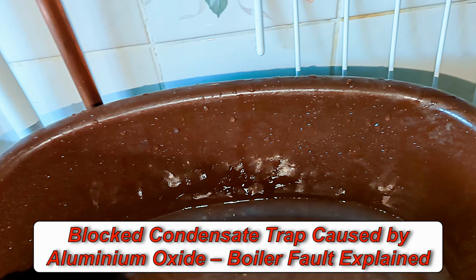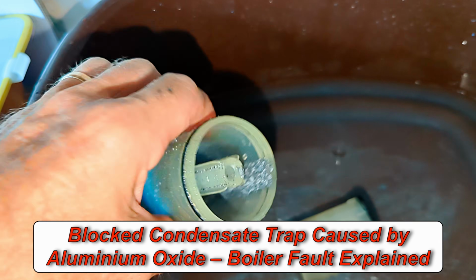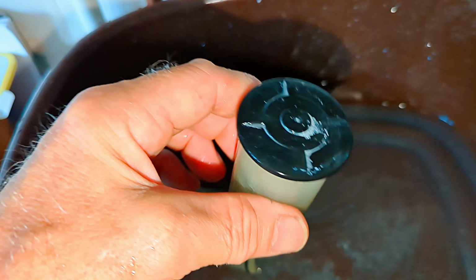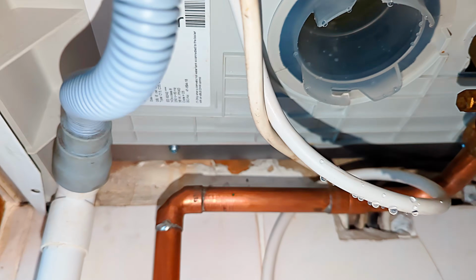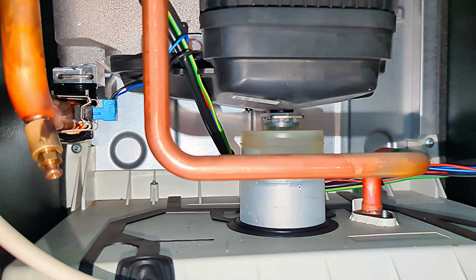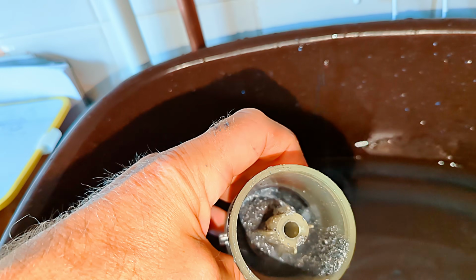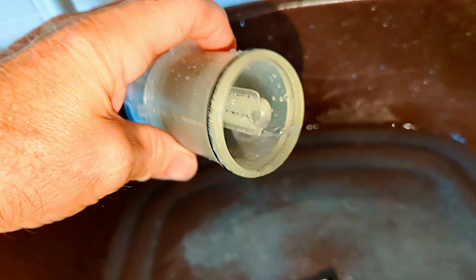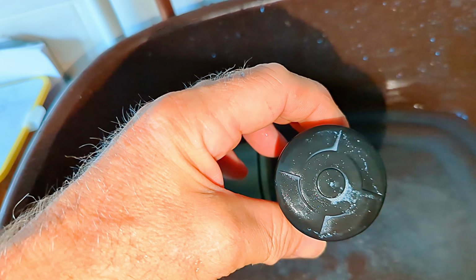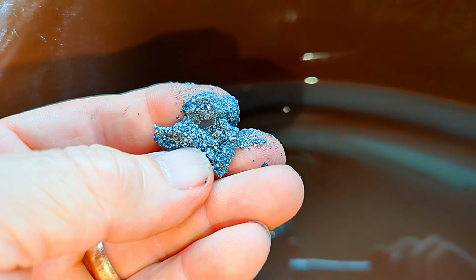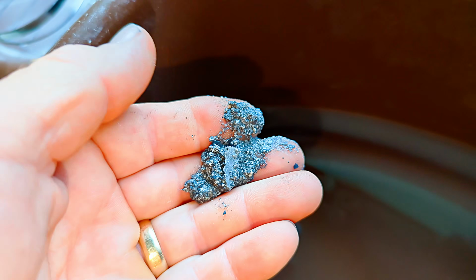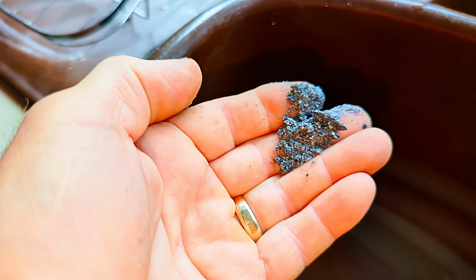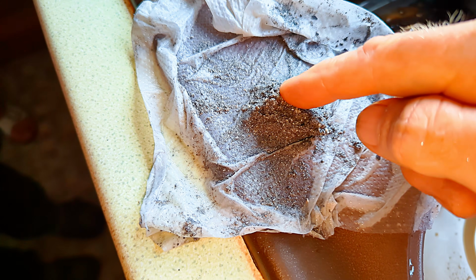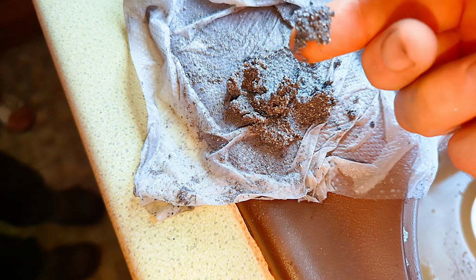Now, a lot of modern boilers use aluminium heat exchangers. I must say I'm not a big fan of aluminium heat exchangers. Now, as the boiler is operating, you've got that condensed water, which is running down through the aluminium heat exchanger. And as it does that, it produces aluminium oxide, which is like a grey sandy material. This grey sandy material then runs into the trap, where when the boiler is serviced, you would clean the trap out.